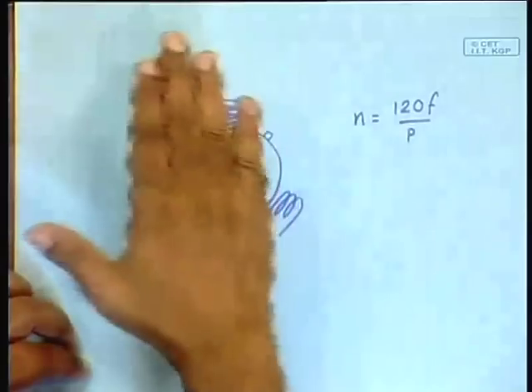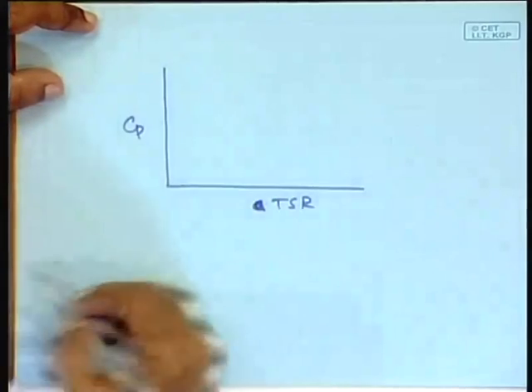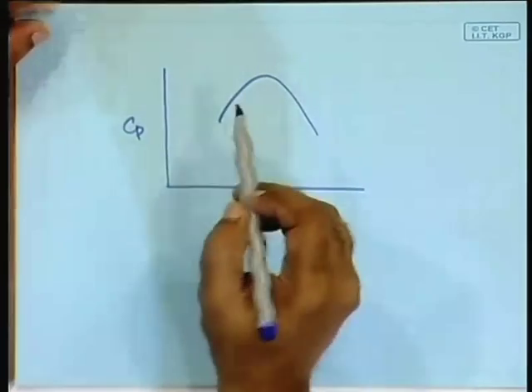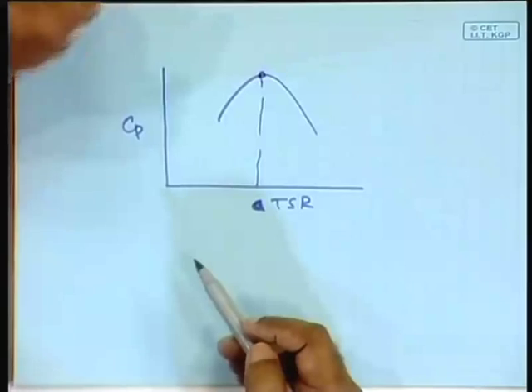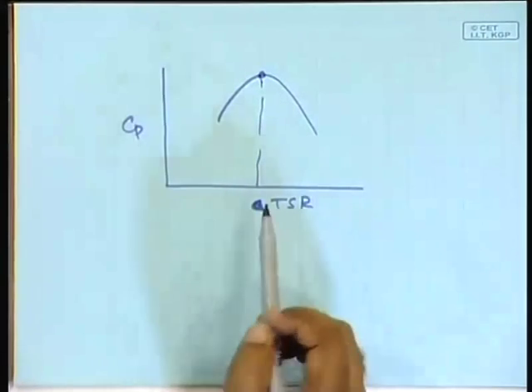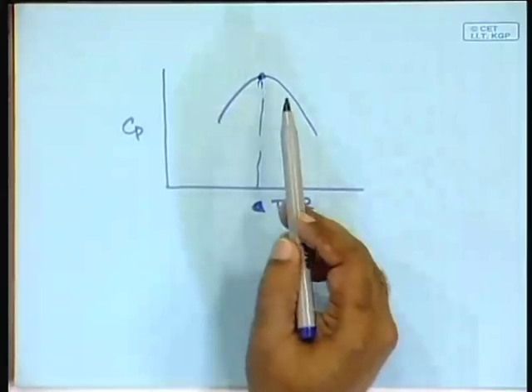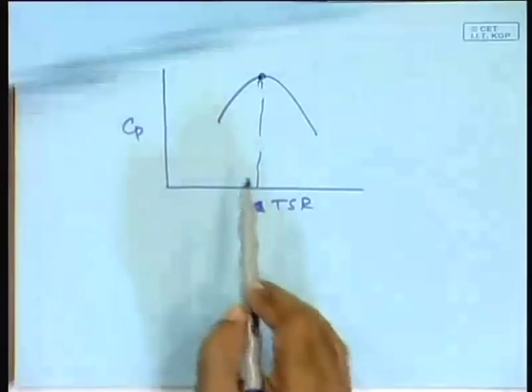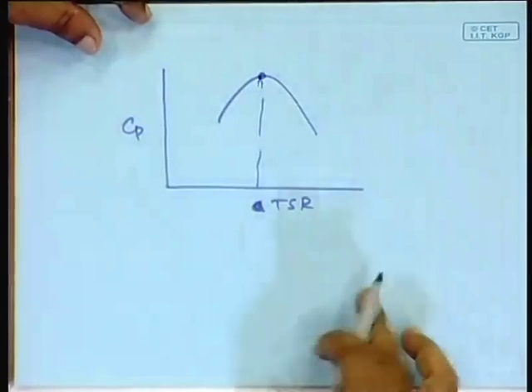Does this match the required character of a wind turbine? In a wind turbine, the tip speed ratio versus Cp characteristic shows you want to operate at a constant TSR to achieve maximum power coefficient. As wind speed changes, you must keep rotational speed proportional to wind speed at the value corresponding to the maximum power point. This means as wind speed changes, you have to change rotational speed — otherwise you cannot track this point. This characteristic actually contradicts the requirement of the wind turbine: a wind turbine should be a variable-speed to constant-frequency generation system.